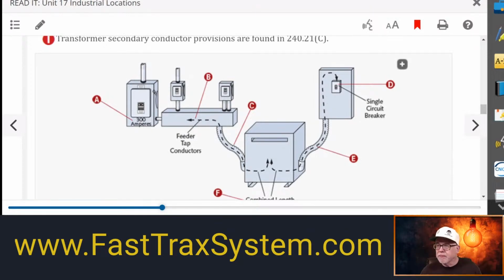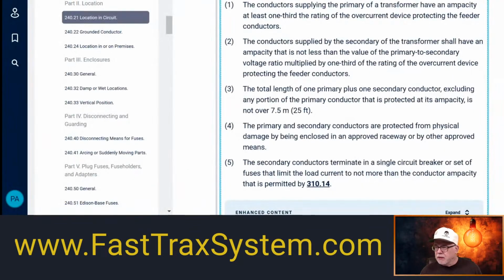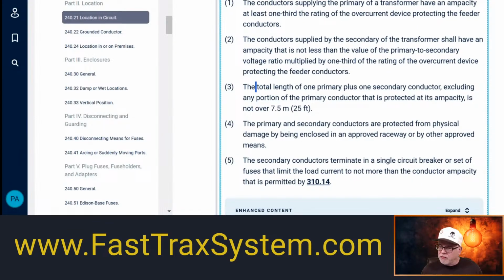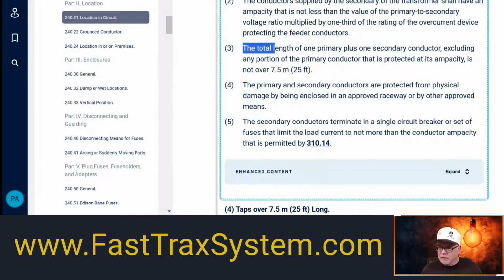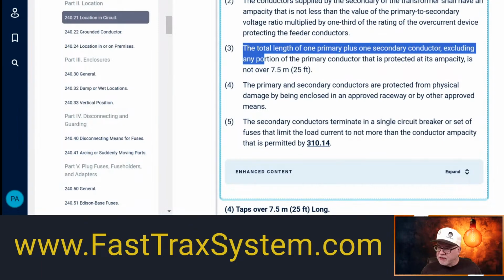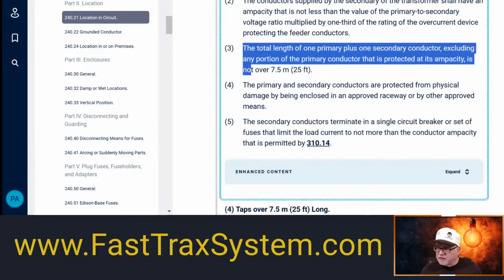Okay, let's get us back to here. Now, third one is we've already covered. This one is the length. The total length of one primary plus the secondary, excluding any portion of the primary conductor that is protected at its ampacity, is not over 25. So that's how we got the combination.